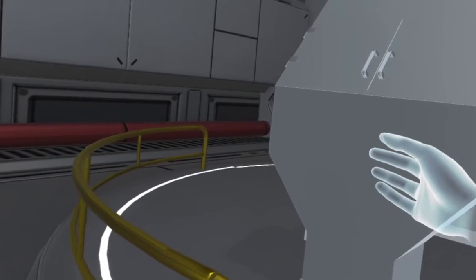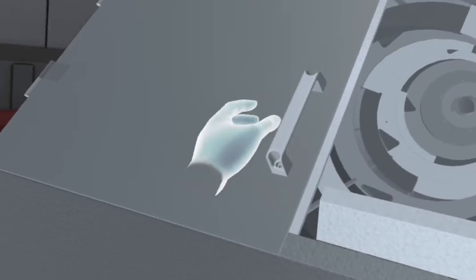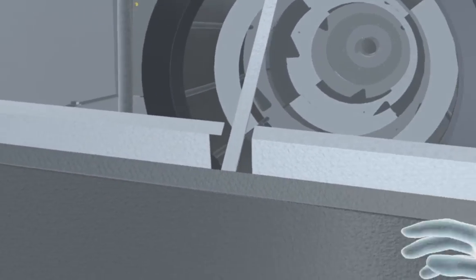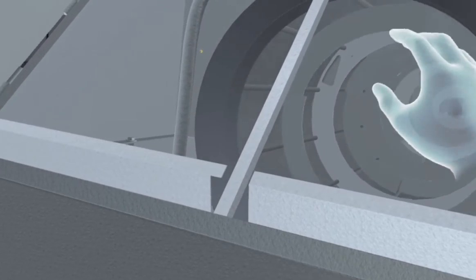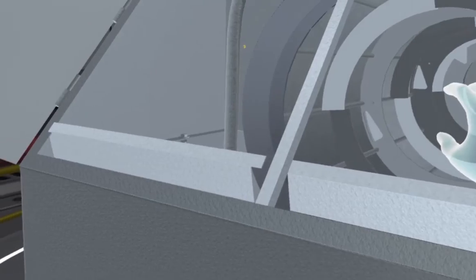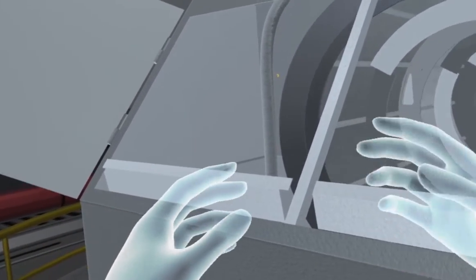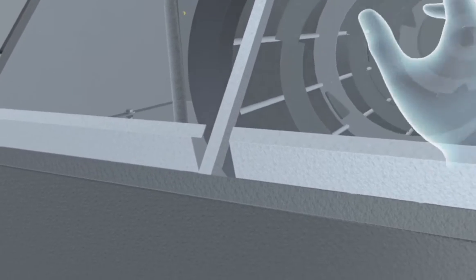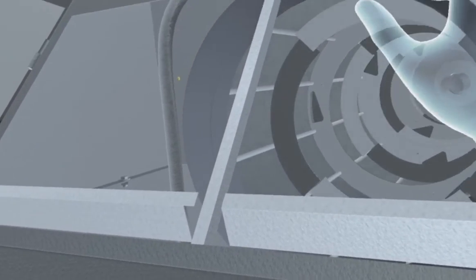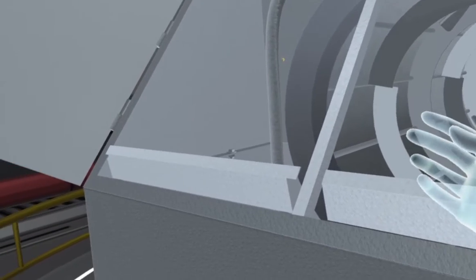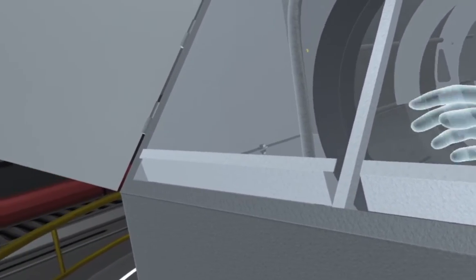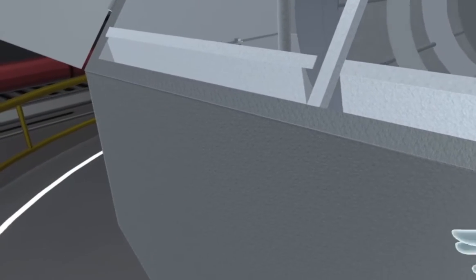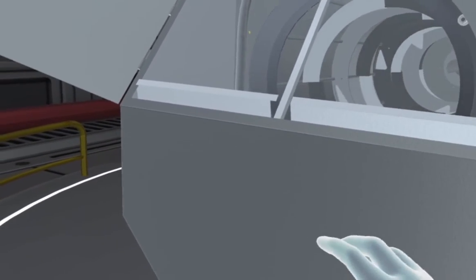So, the first is really the access points, and we see that we have these two big access doors here at the end. And this is nice to be able to take samples of your effluent sludge. And also, a big part of this is being able to see the sludge itself and how it's reacting to the polymer. And that's really how you do your polymer dosing, is you're looking at the sludge and you're seeing how it's reacting. Is it too thin because the polymer is too low, or is the polymer dose too high and causing blinding of the screen, and you see that there's no water release, that sort of thing. So that's what's nice about having this visual here at the end of the RDT.